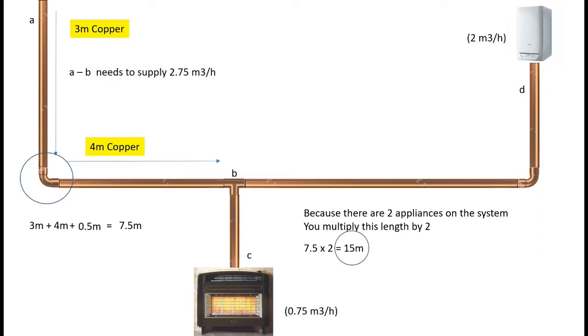Now, you've got the two numbers that you need to do your pipe sizing. You've got 15 meters of pipe, and you've got 2.75 meters cubed per hour to go through it. They're the only two numbers you need to pipe size. You then go to your chart in the Viper book, and it will show you the size of pipe that you need.